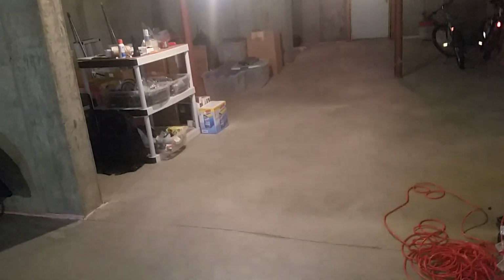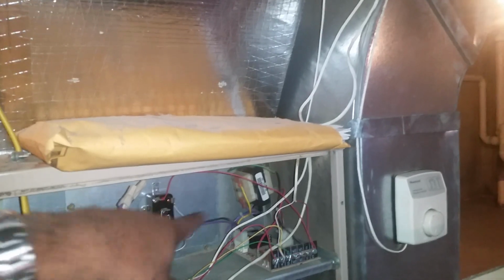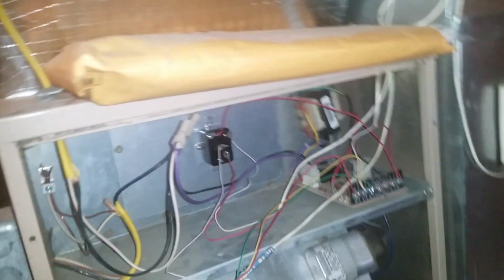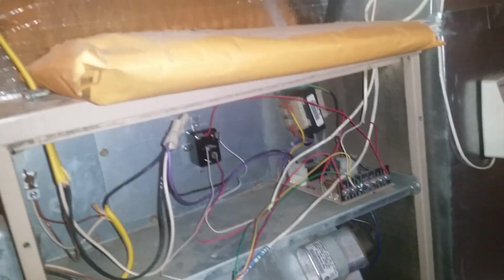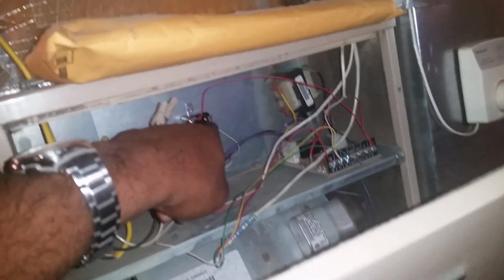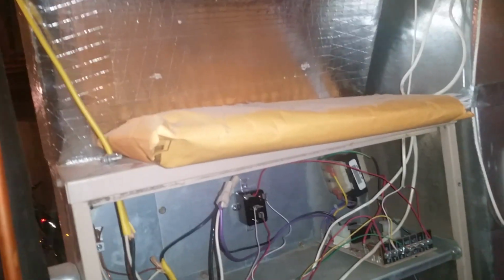I also checked the thermostat, and the thermostat was okay. When the signal comes from the thermostat to the relay switch asking for heat, the relay switch will turn on the circulator. So that's another signal to you that your thermostat is working fine. It's asking for heat correctly, because that signal comes here and then your relay switch turns on the circulator.